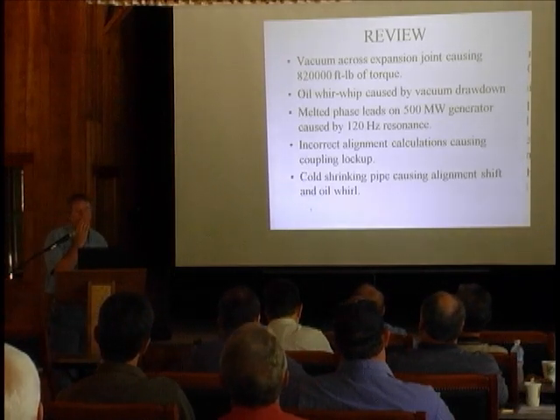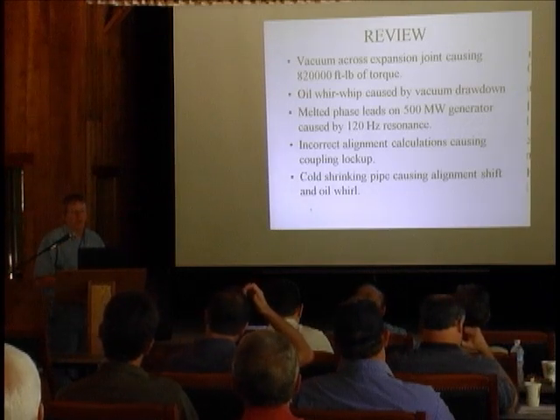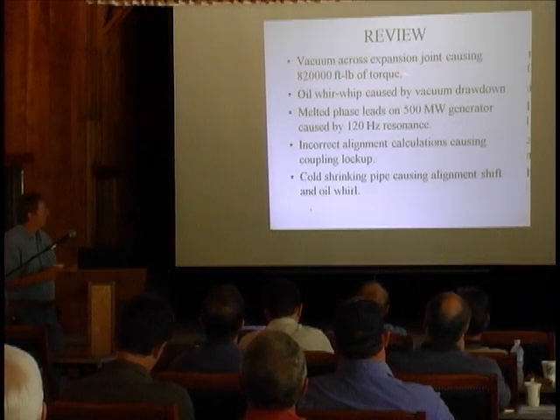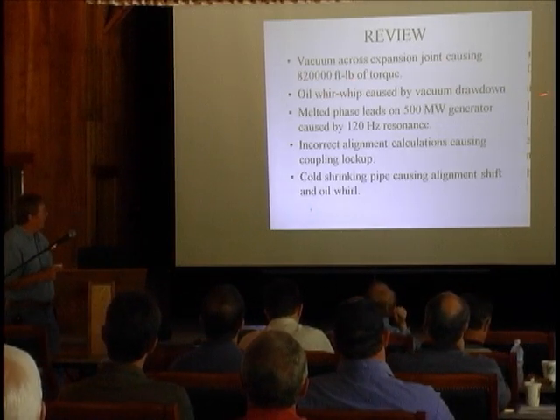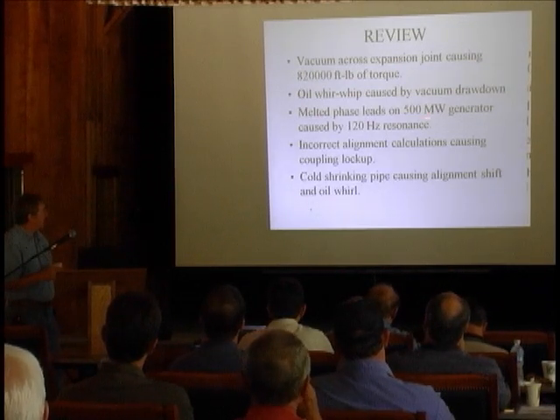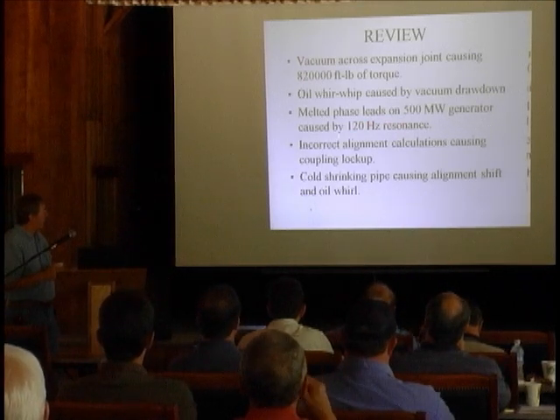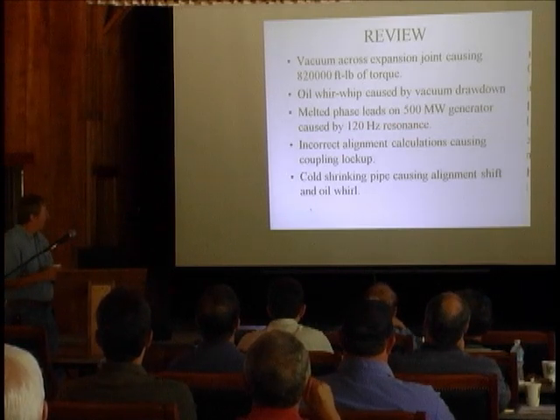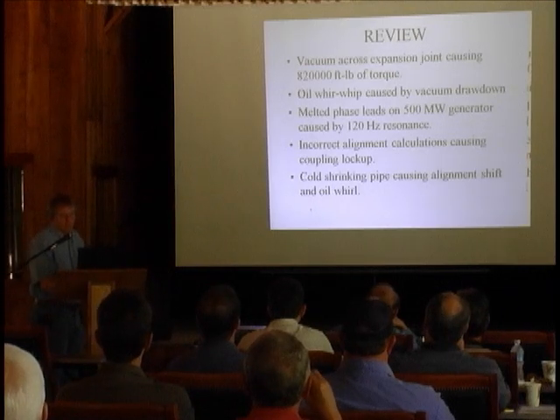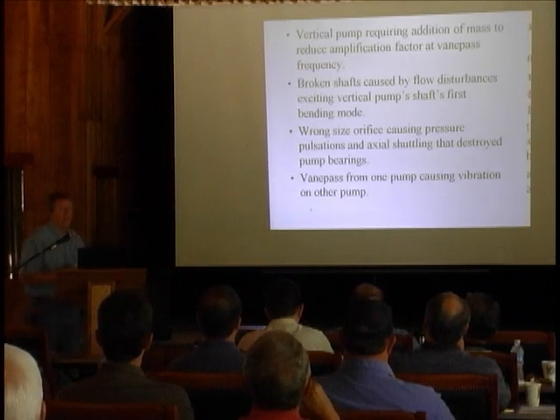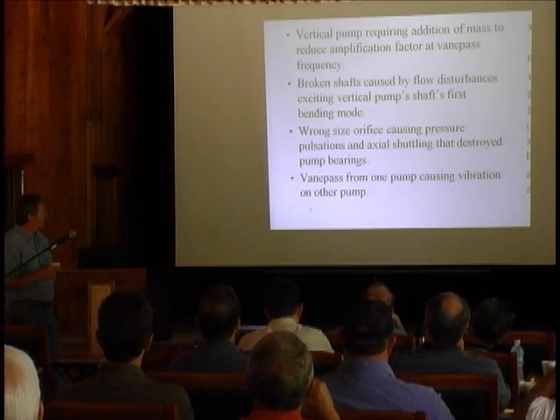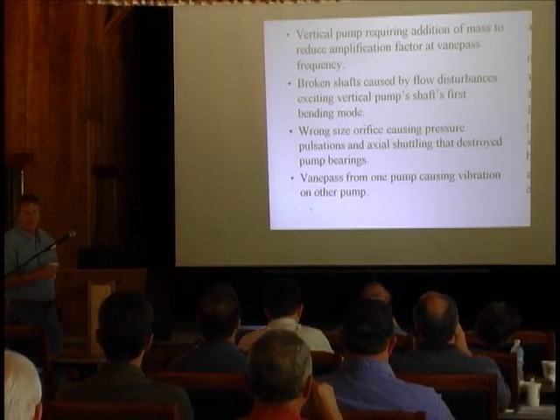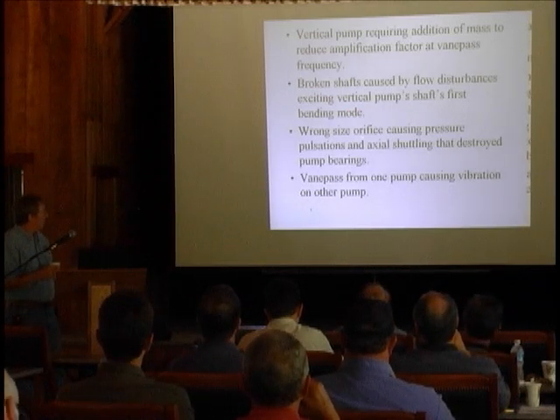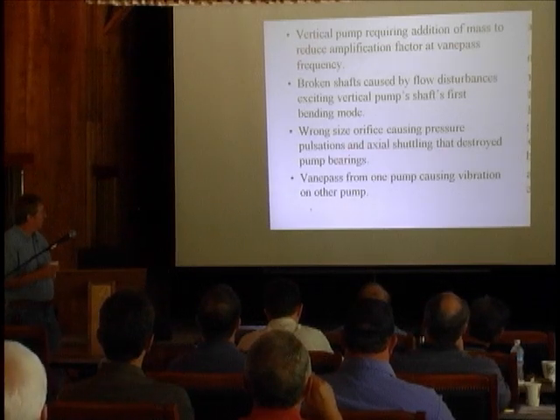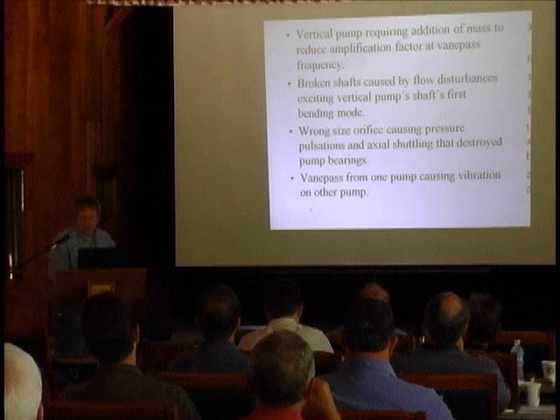So a little bit of review here. We talked about the vacuum across an expansion joint causing 820,000 pound-feet of torque. Again, you've got to watch those expansion joints. Oil whirl and whip caused by vacuum drawdown. Melted phase leads caused by resonance. Incorrect alignment calculations, not taking everything into effect. Cold shrink and piping caused an alignment shift. Vertical pump, where we had to add mass to the motor to change the amplification factor. Broken shafts, mainly because the guy had bought pirate parts. Then the wrong size orifice causing pressure pulsations, axial shuttling that destroyed the bearings. And then vane pass from one pump's vibration causing a vibration on another pump.